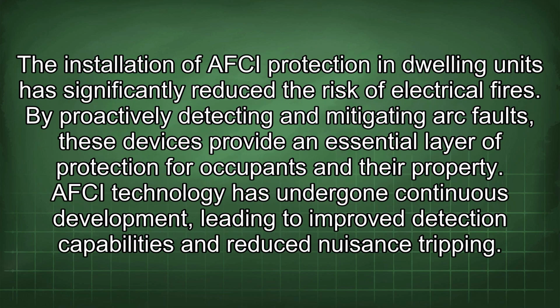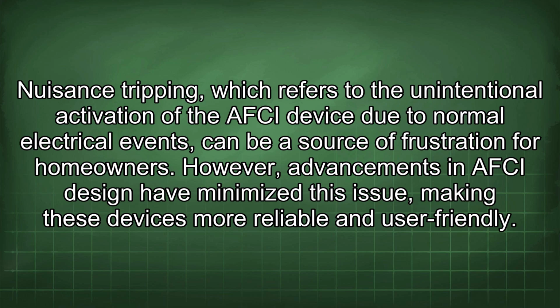The installation of AFCI protection in dwelling units has significantly reduced the risk of electrical fires. By proactively detecting and mitigating arc faults, these devices provide an essential layer of protection for occupants and their property. AFCI technology has undergone continuous development, leading to improved detection capabilities and reduced nuisance tripping. Nuisance tripping, which refers to the unintentional activation of the AFCI device due to normal electrical events, can be a source of frustration for homeowners. However, advancements in AFCI design have minimized this issue, making these devices more reliable and user-friendly.